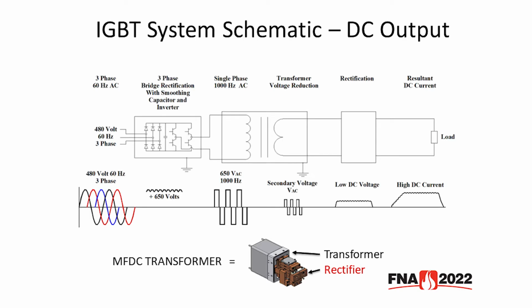So, how does an IGBT MFDC power supply work? Here's an IGBT MFDC pictorial schematic. Starting on the left side, the input into the system is 3 phases, 60 Hz AC. This shows 480 volts, but other main voltages can be used. Within the control, the power is first rectified to a 650 volt single-phase DC bus. It is then smoothed with a capacitor and inverted with IGBTs into mid-frequency. The output of the control is 650 volts at 1000 Hz.